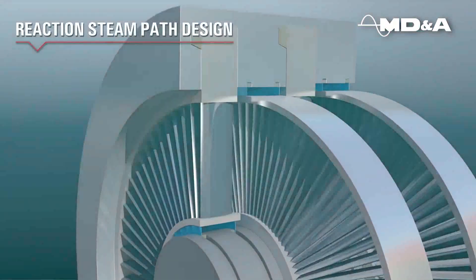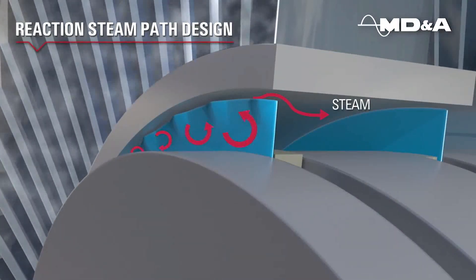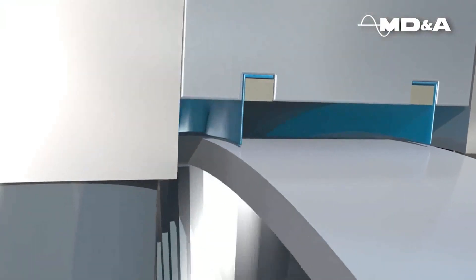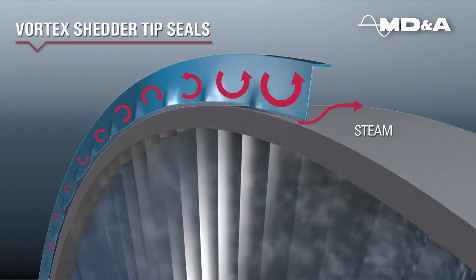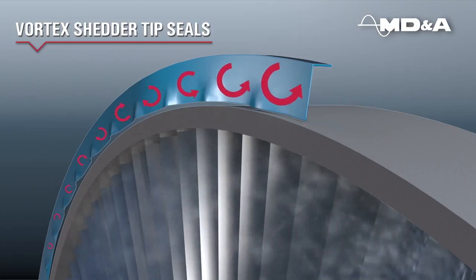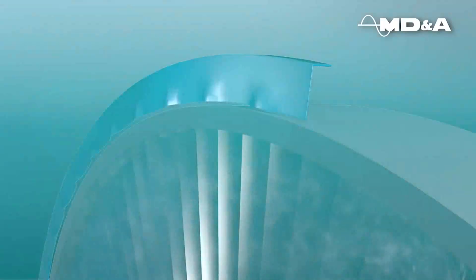The vortex shedder also operates on a reaction steam path design, where it can be applied to the rotating seal strip and the stationary seal strip. These vortices increase the pressure drop, resulting in lower flow and less leakage across the seal. This translates to improved stage heat rate performance for the steam turbine.